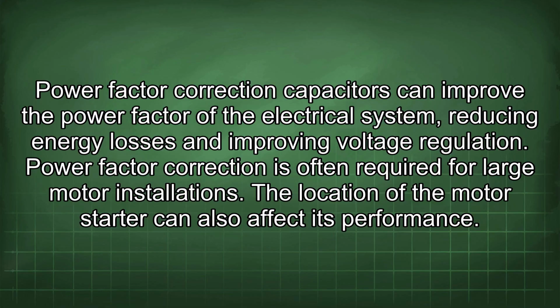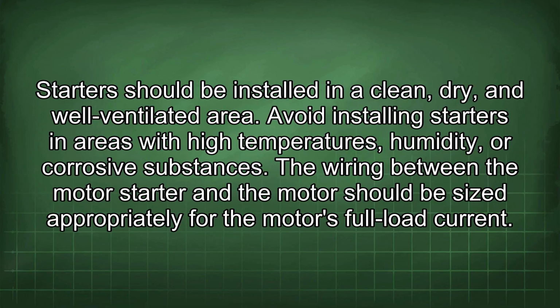The location of the motor starter can also affect its performance. Starters should be installed in a clean, dry, and well-ventilated area. Avoid installing starters in areas with high temperatures, humidity, or corrosive substances.